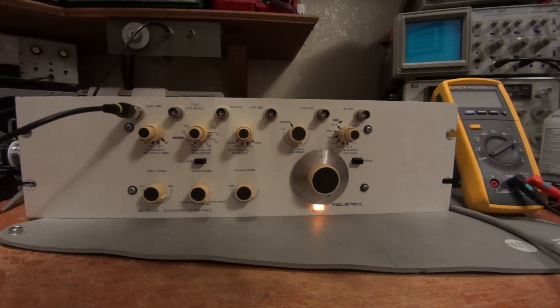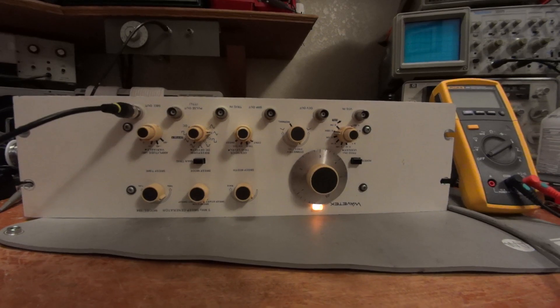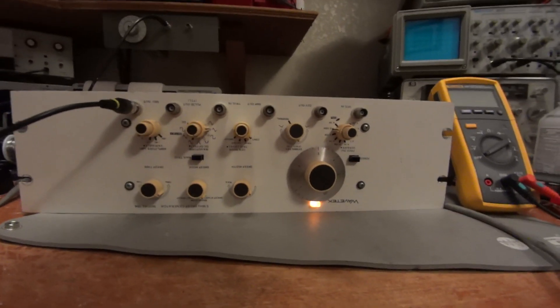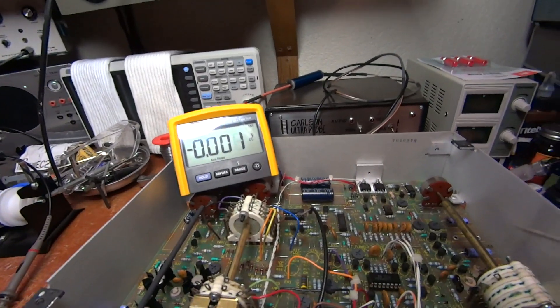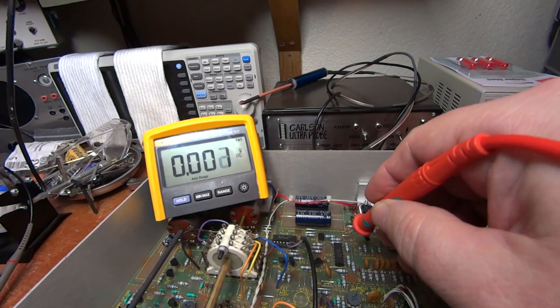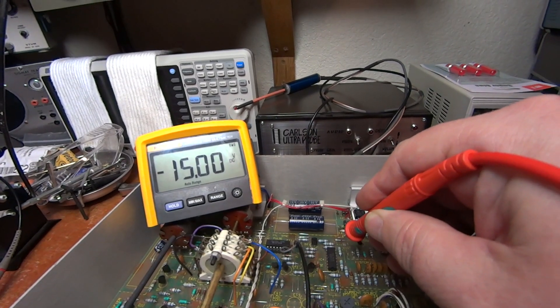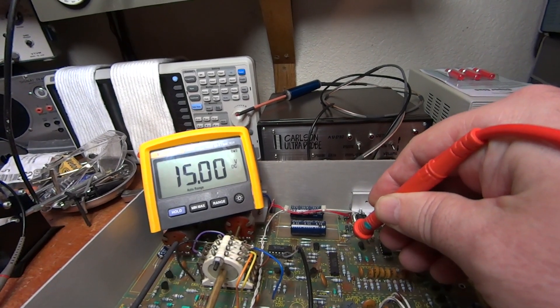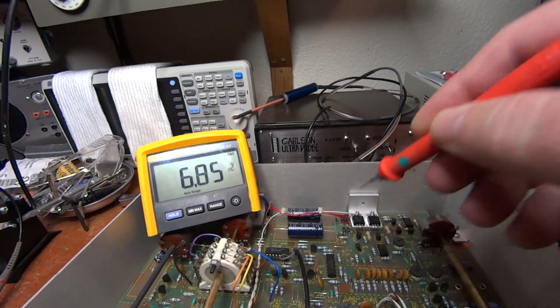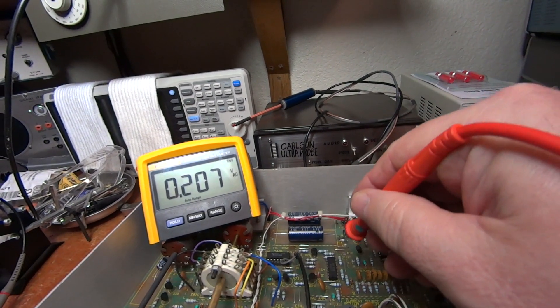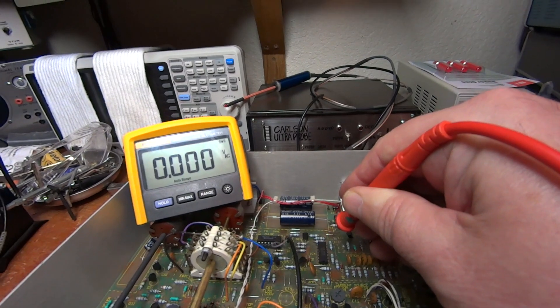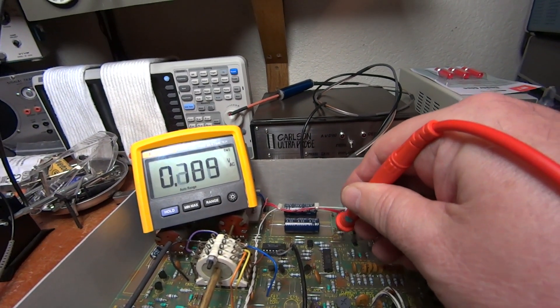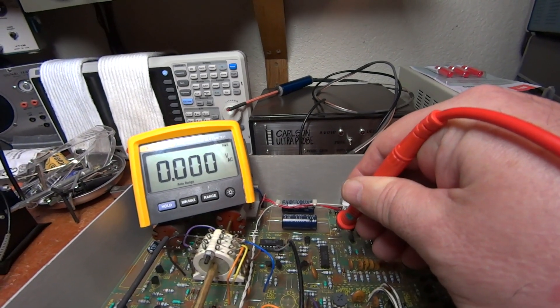When I took a look at the power supply, the power supply looked good. I'm going to show you what I mean by that. When I probe the rails, they're supposed to be positive and negative 15 volts. That's the negative 15 volt rail and this is the positive 15 volt rail. Everything looks pretty good. Let's see if there's some ripple on there. I'm going to switch over to AC voltage and probe this again. Look at that, there's no AC on that power supply at all. Absolutely wonderful. There's no AC on the positive rail either. Isn't that nice?